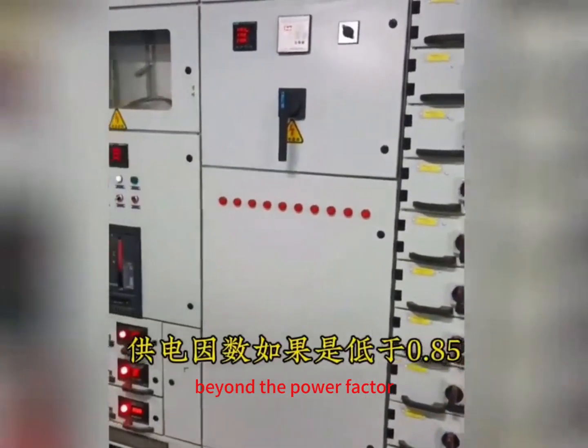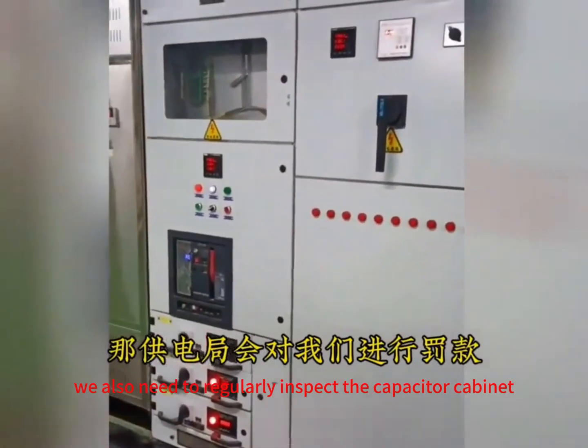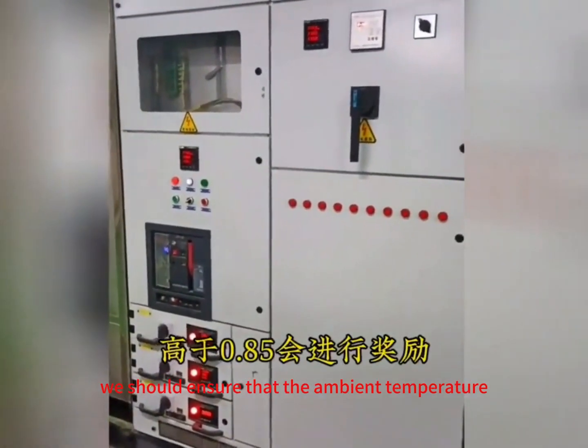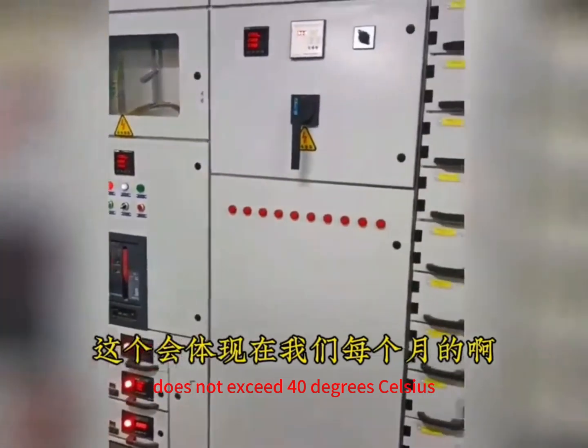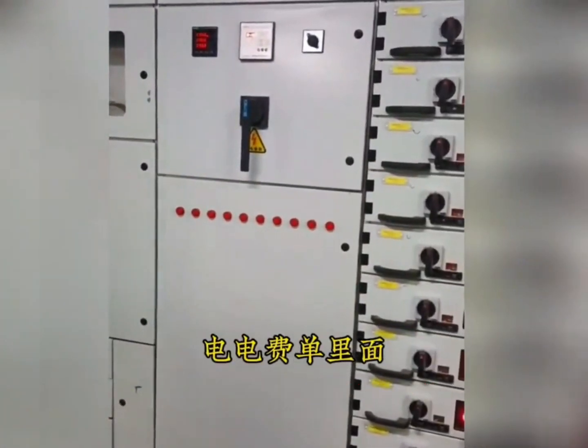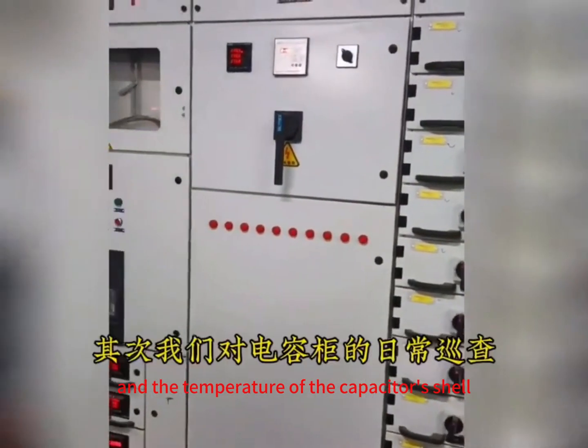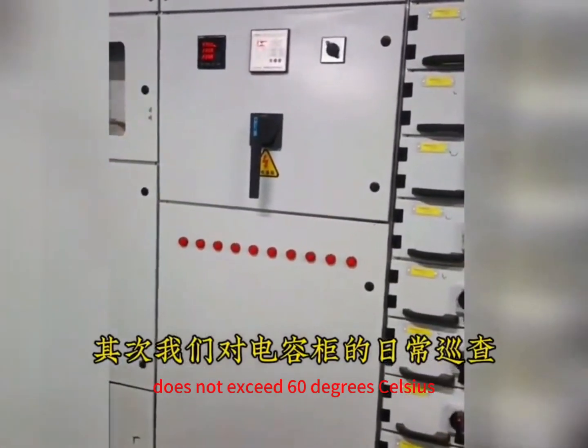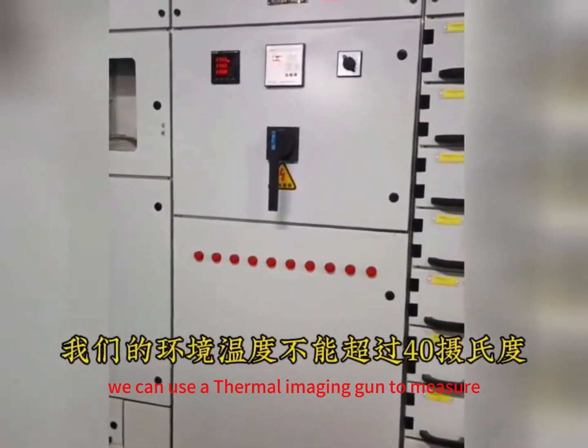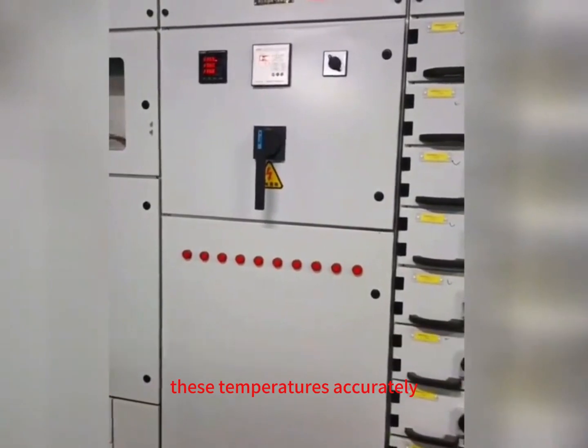Beyond the power factor, we also need to regularly inspect the capacitor cabinet. We should ensure that the ambient temperature does not exceed 40 degrees Celsius and the temperature of the capacitor's shell does not exceed 60 degrees Celsius. We can use a thermal imaging gun to measure these temperatures accurately.